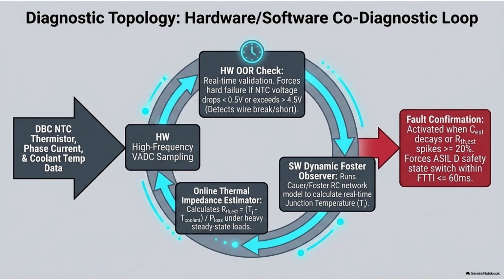So the car's computer might think everything is fine, the pump is running at 100%, the fluid is flowing perfectly, there are no leaks. But the system is still overheating because the heat literally cannot cross that crusty barrier to get into the liquid. Exactly. The thermal resistance of the entire liquid cooling loop increases drastically, but totally invisibly. The heat backs up into the aluminum, which backs up into the copper, which backs up into the silicon chip, and you get a failure.